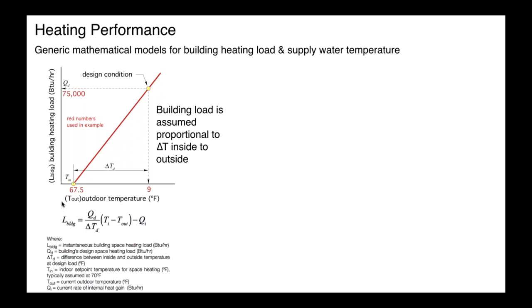The graph here, actually this graph is for a building we're going to talk about in Boston. It has a design heating load of 75,000 BTUs per hour. So that's our design load point. And that corresponds to an outdoor temperature of 9 degrees in that location. So that's just, again, a simple linear model.